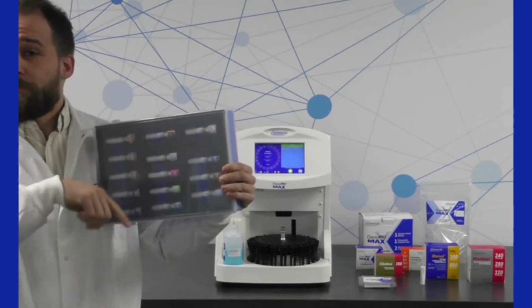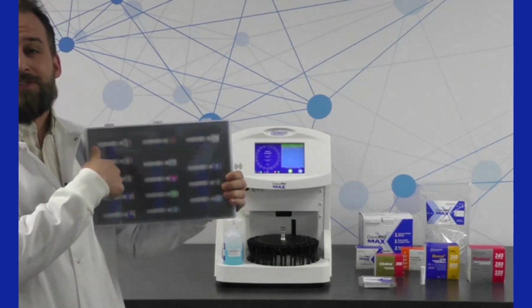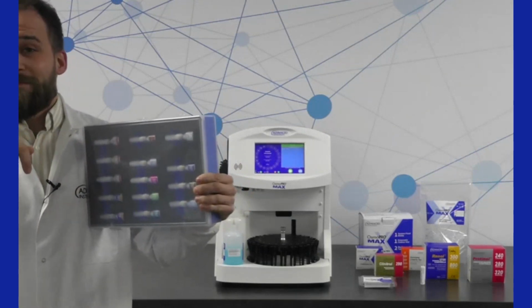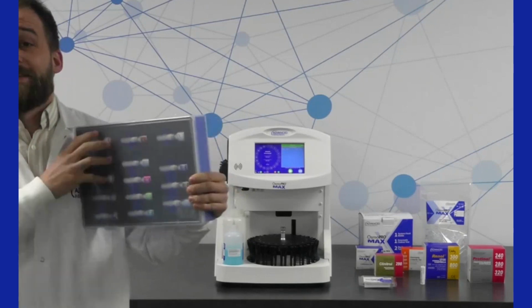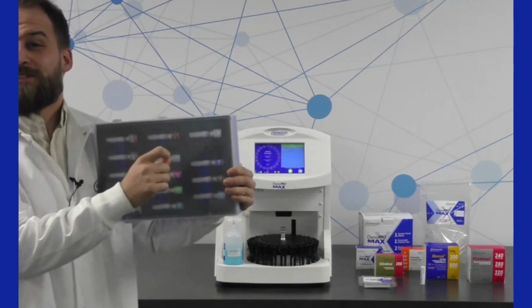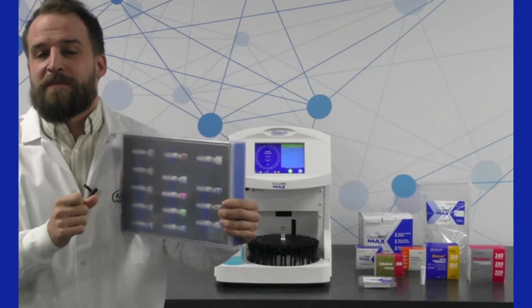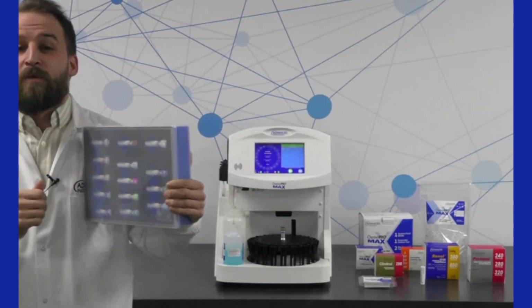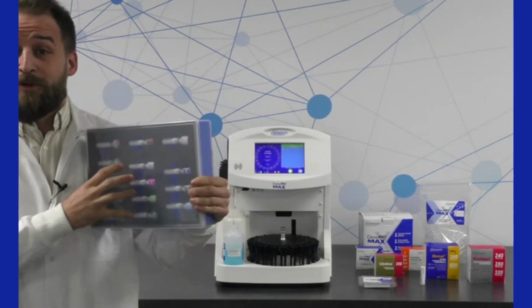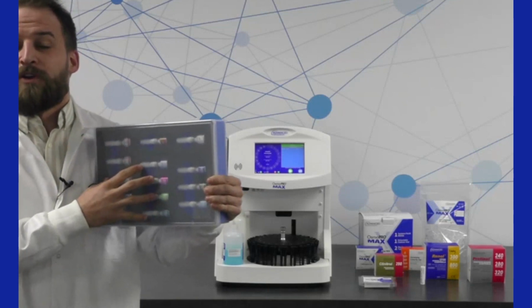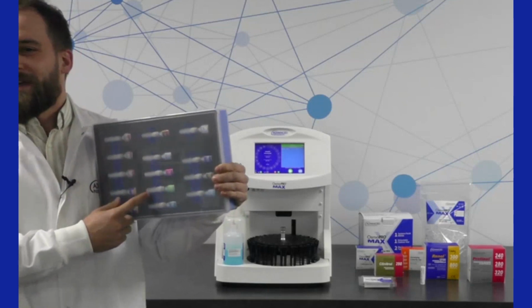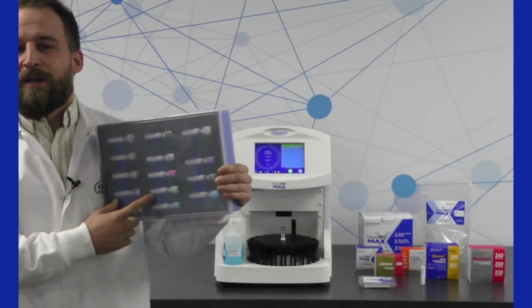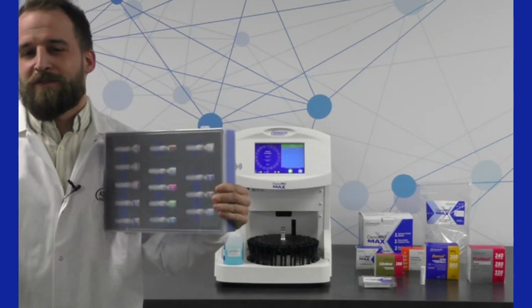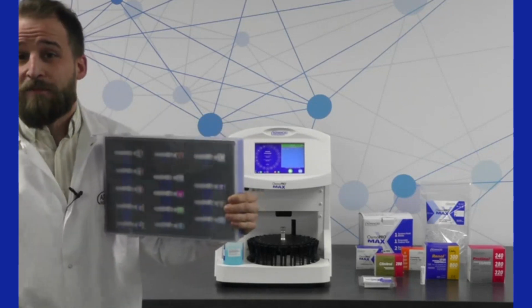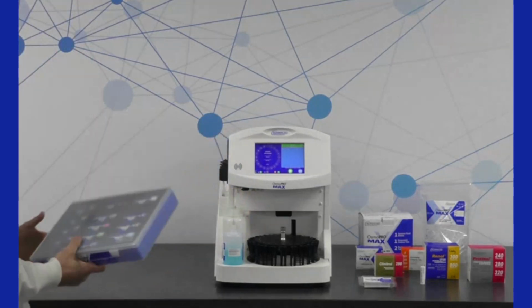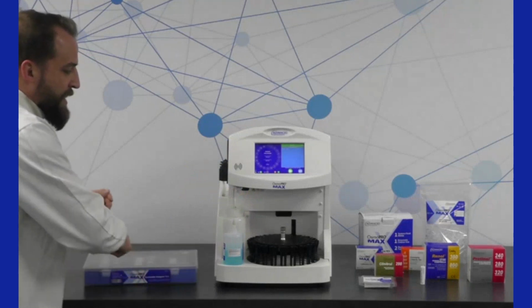And then the barcode that's wrapped all the way around each of these adapters will tell the instrument what you've put in each position. It will also make it easier, because those step-by-step instructions that I was describing for calibration and for the Max 500 maintenance kit will also tell you what adapter to put in what position on the turntable when you're going through that process. So it's just another thing that makes everything that much easier when you're performing things that are maybe out of what's considered routine, like a calibration or a 500 test maintenance. So I just wanted to mention that as well.